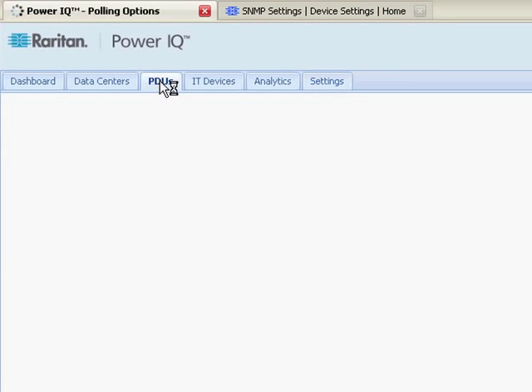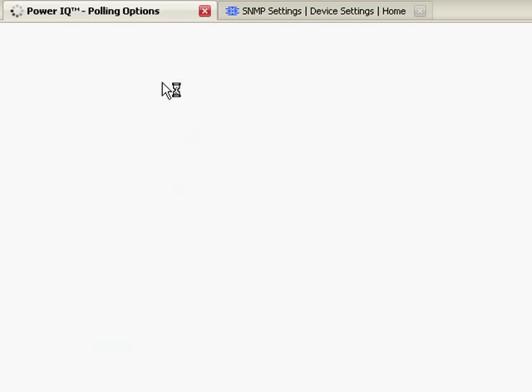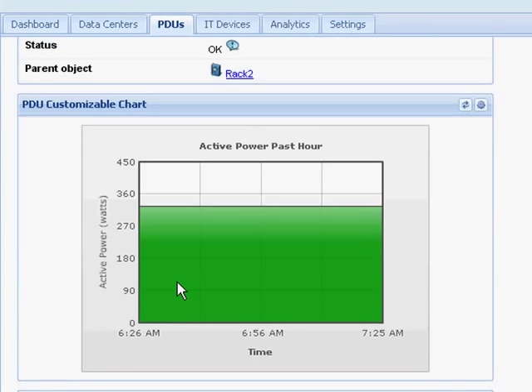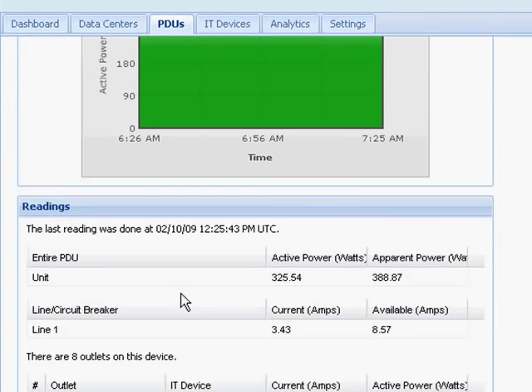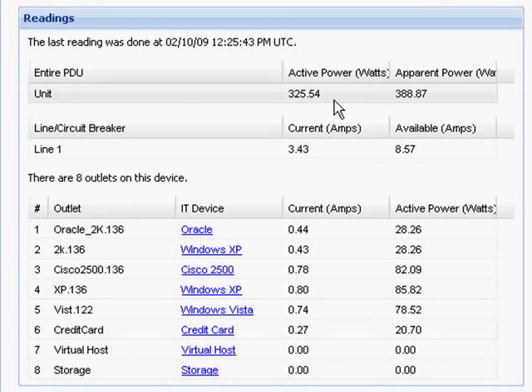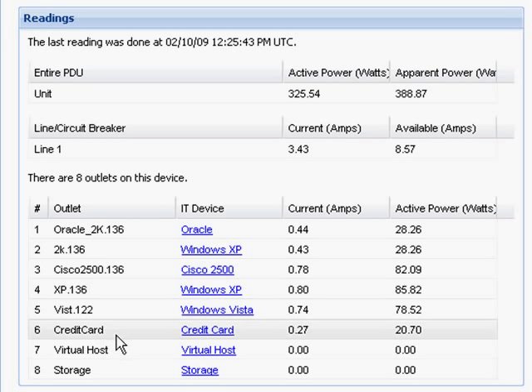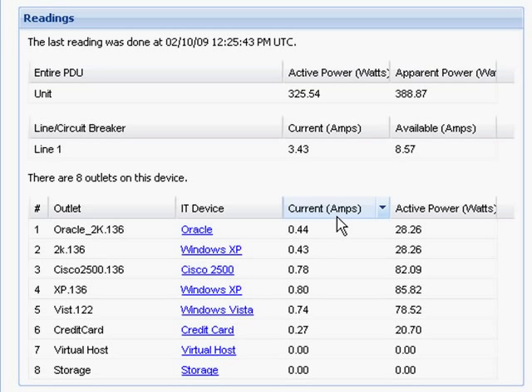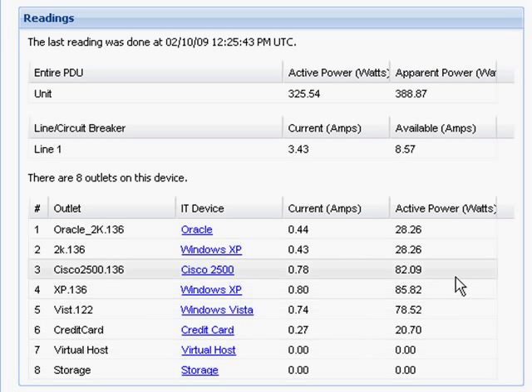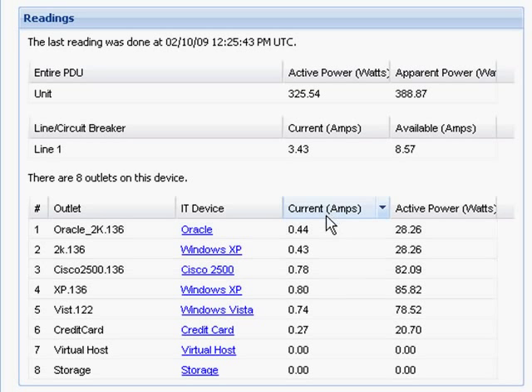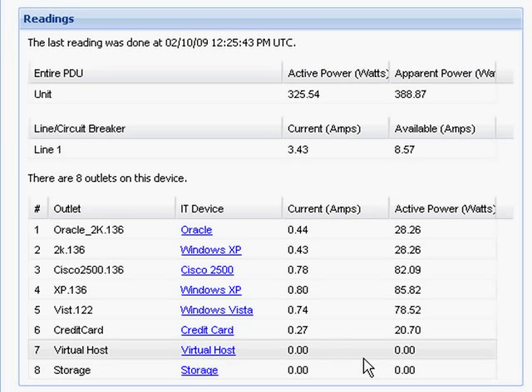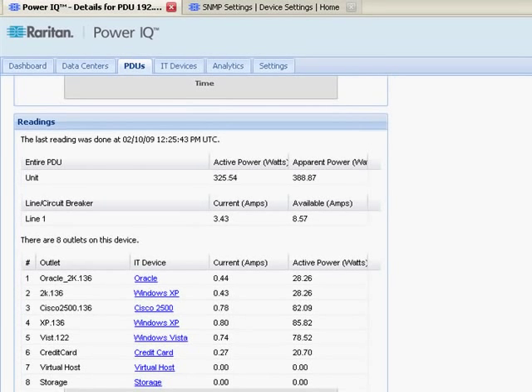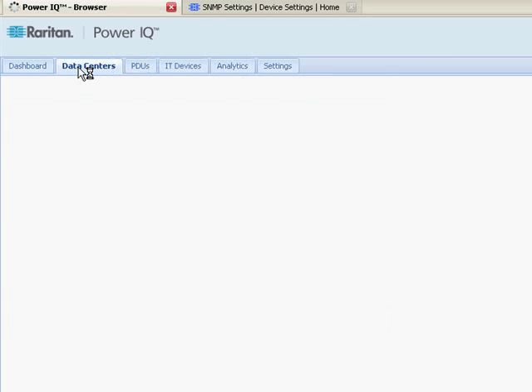Now if I go back to my PDU page, and I click the IP address, next level of detail is, am I getting my entire active power data, am I recording outlet names for my PDUs, am I getting individual current or active power readings? If I'm not getting individual outlet readings, again, I go back to my network configuration, my SNMP settings, and make sure that that's all working. But now if I've looked at this and I'm getting these types of readings, now I'm pretty confident that my analytics should work, provided I configure it correctly.